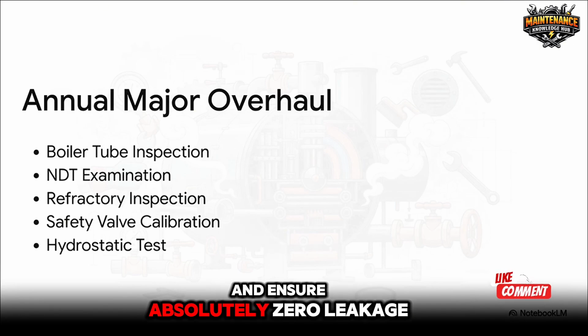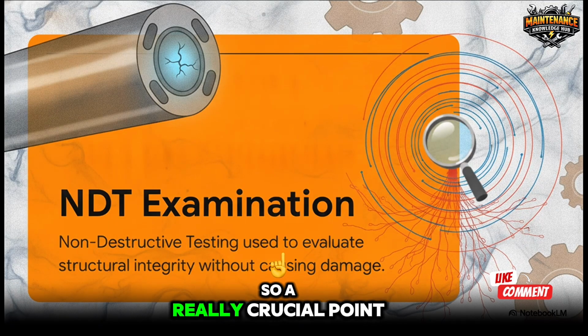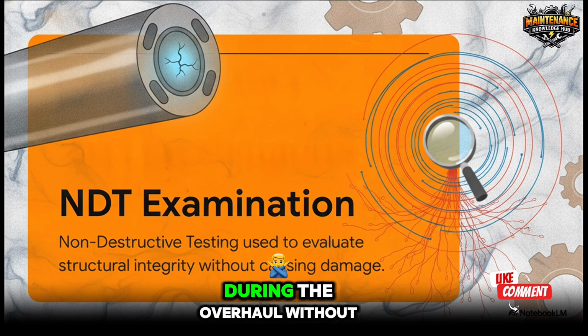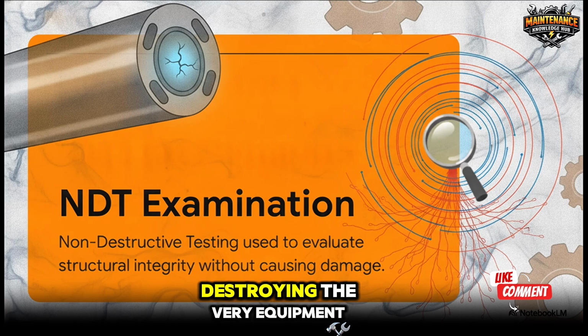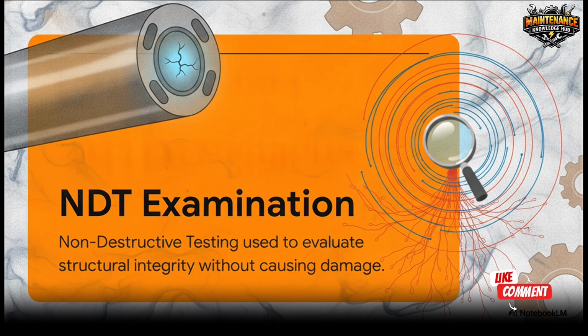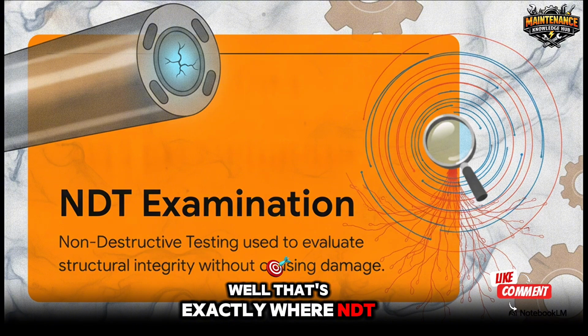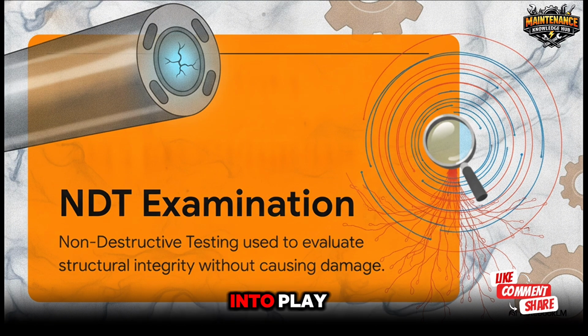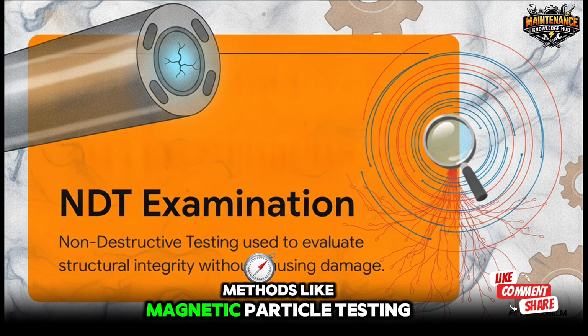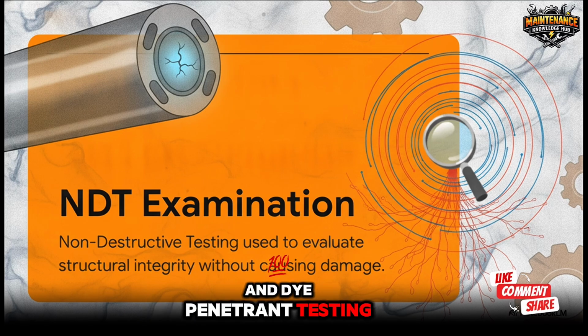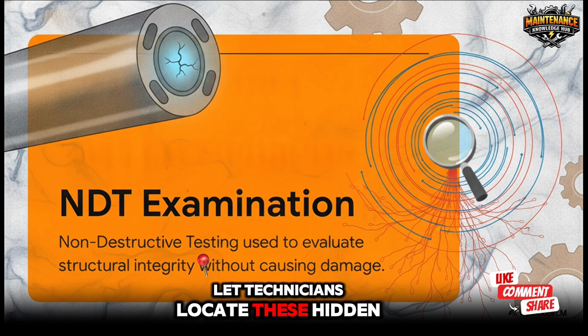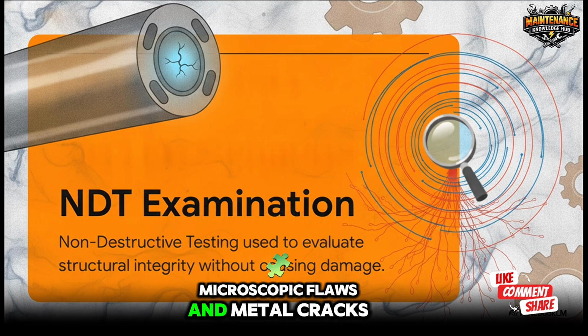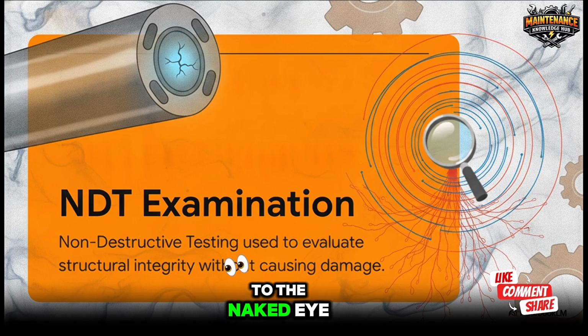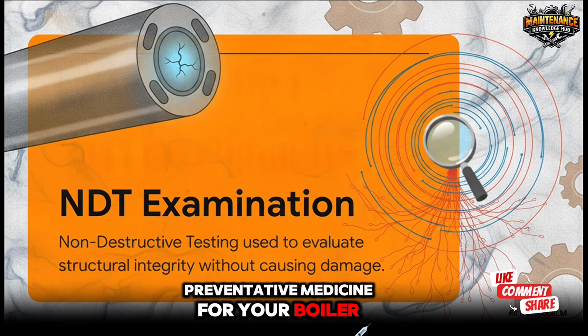ensure absolutely zero leakage. So a really crucial point here is, how do we actually inspect those tubes during the overhaul without destroying the very equipment we're trying to save? Well, that's exactly where NDT, or non-destructive testing, comes into play. Methods like magnetic particle testing and dye-penetrant testing let technicians locate these hidden, microscopic flaws and metal cracks that are totally invisible to the naked eye. It's basically high-tech, preventative medicine for your boiler.